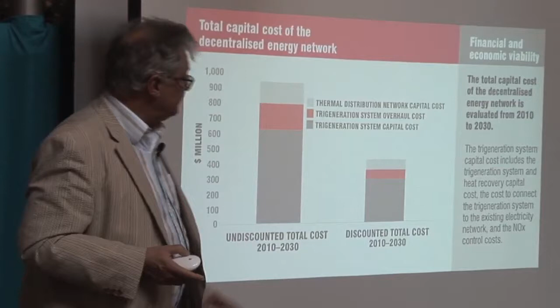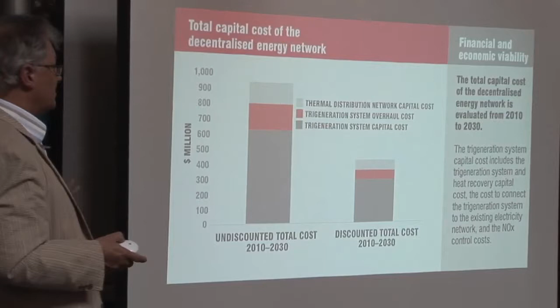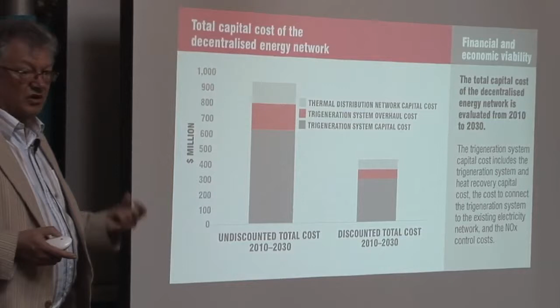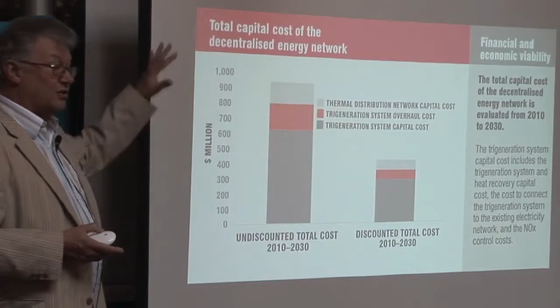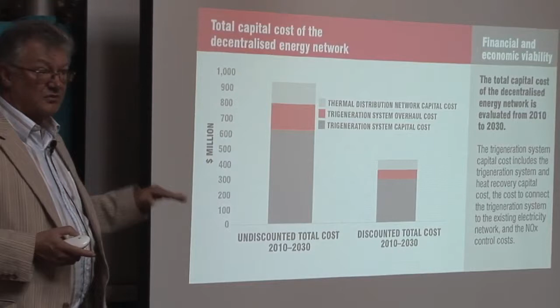They pretty soon learned that the 45% electrical efficiency was far better than 36% for coal, and pretty much on a par with combined cycle gas turbines. But in addition, two-thirds of the primary energy was now being captured and put to good use for heating and cooling, and also displacing electricity consumption, particularly peak, which is such a big problem for the distribution company.